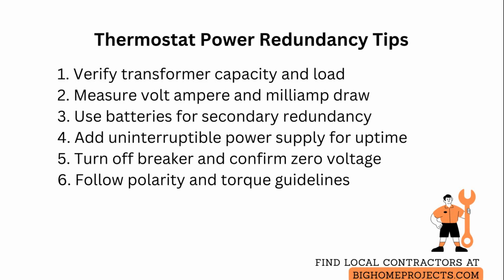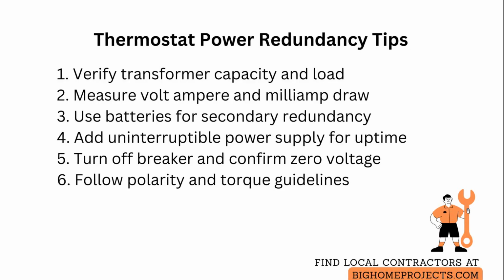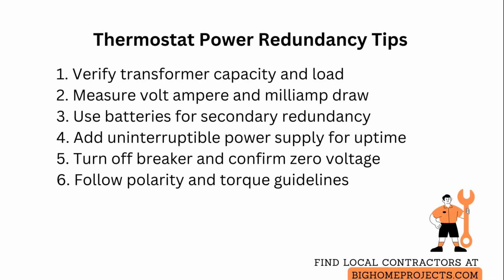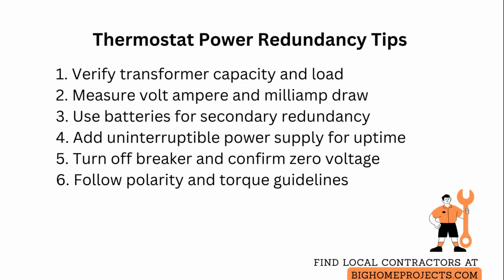For installations where uptime is critical, consider adding a small uninterruptible power supply or a dedicated auxiliary transformer sized for peak loads in addition to batteries. This keeps network hubs and smart controllers stable during longer interruptions.